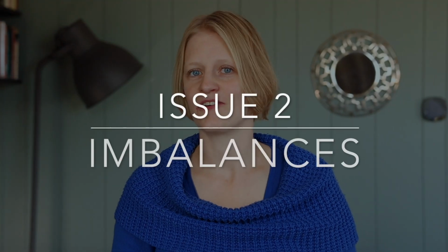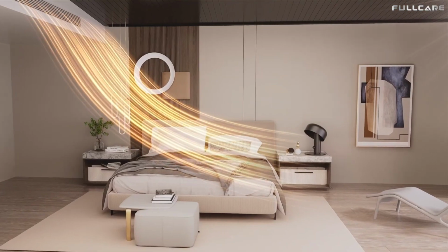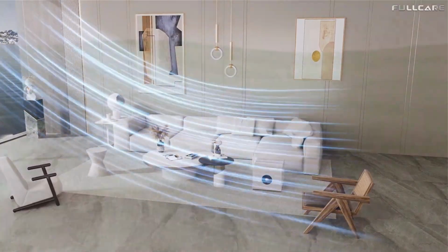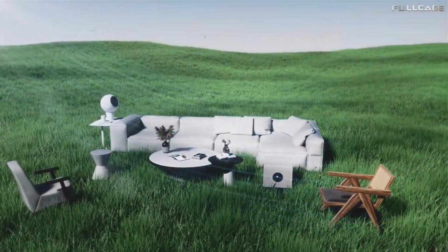Oversized heat pumps can also lead to temperature imbalances in your home. They might heat or cool the space too quickly, leaving some areas too hot or some areas too cold. This inconsistent temperature control not only affects your comfort, but also prompts the system to work harder than necessary to maintain a steady temperature.